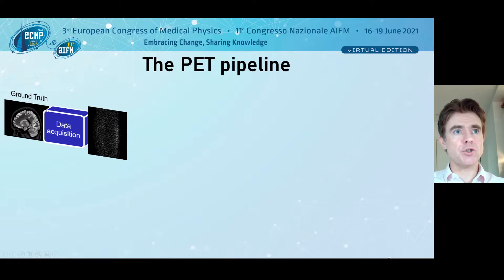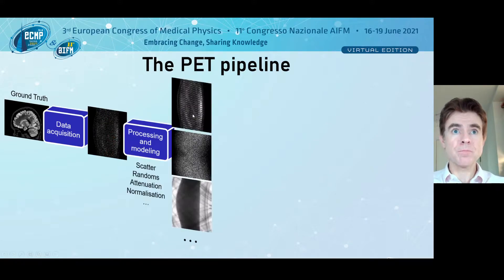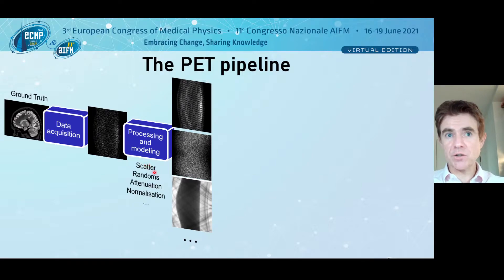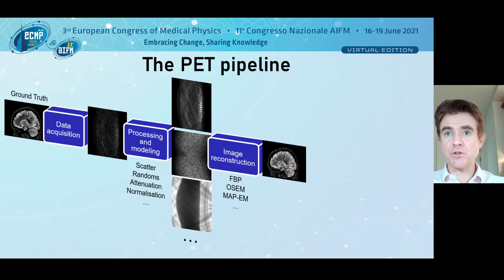This is a conventional data acquisition from a PET scanner. Here I've got a simulation of an FDG distribution inside the scanner. What we get typically are sinograms or projections that look a little bit like this Poisson distributed noisy case shown here. Then what is typically involved is the need to model scatter, randoms, effects of attenuation and normalization in order to get a set of sinograms, which can then be put into the image reconstruction algorithm. This could be a direct method like filtered back projection or more commonly iterative methods to get a reconstructed image.